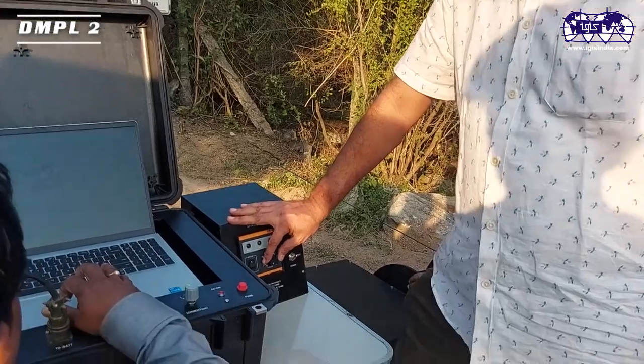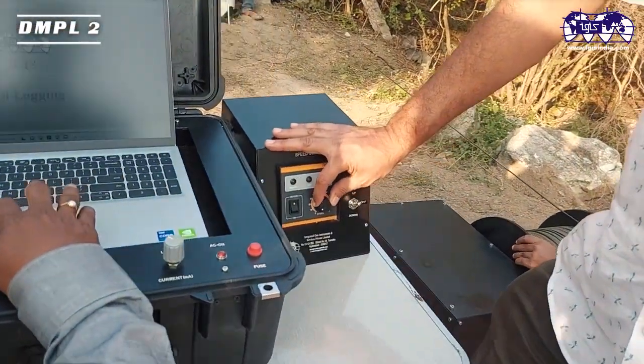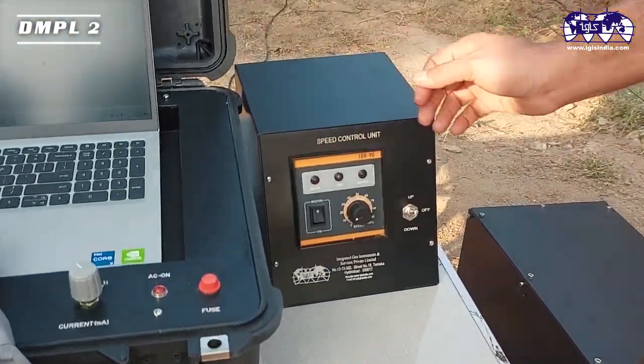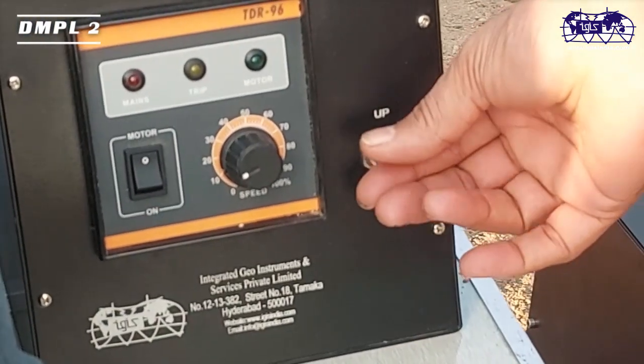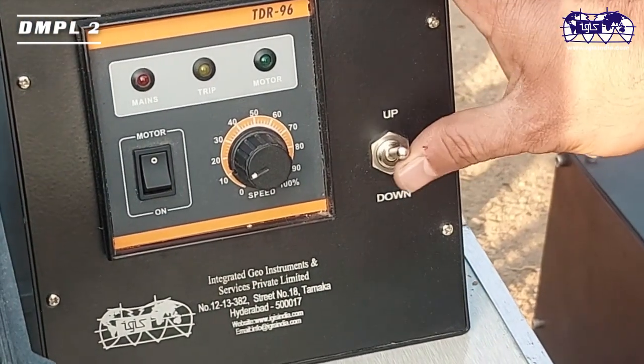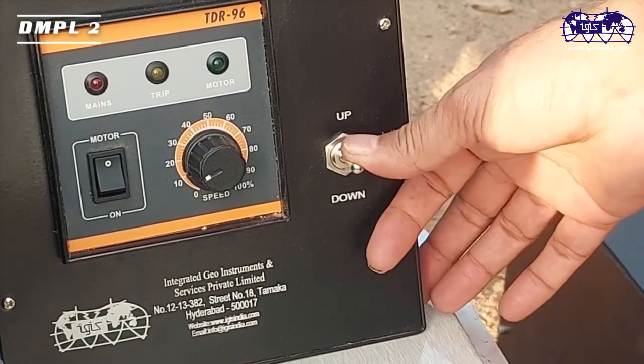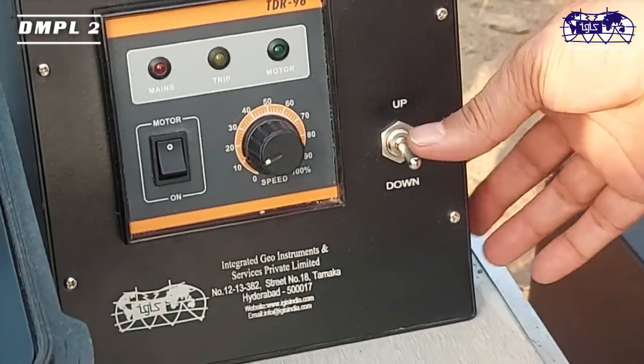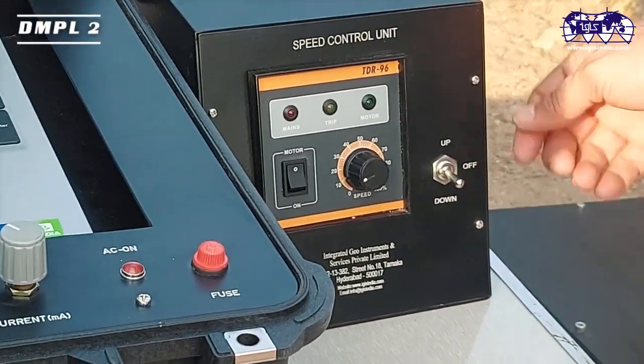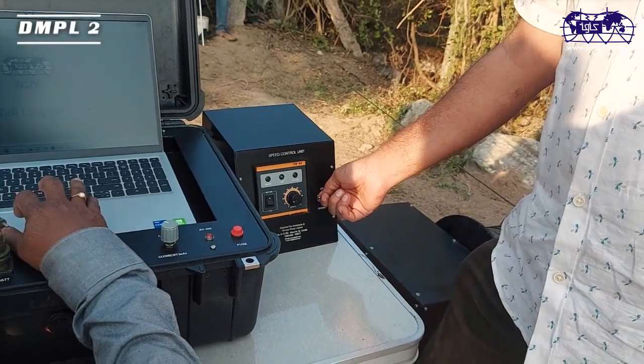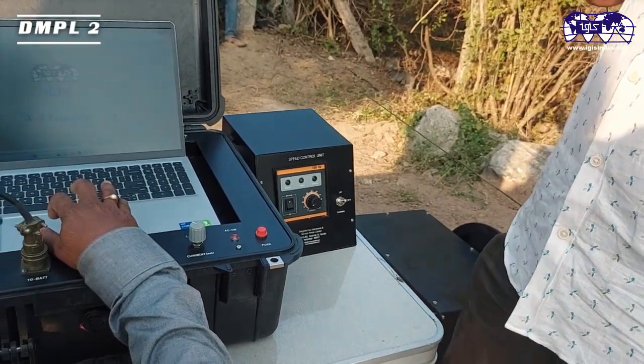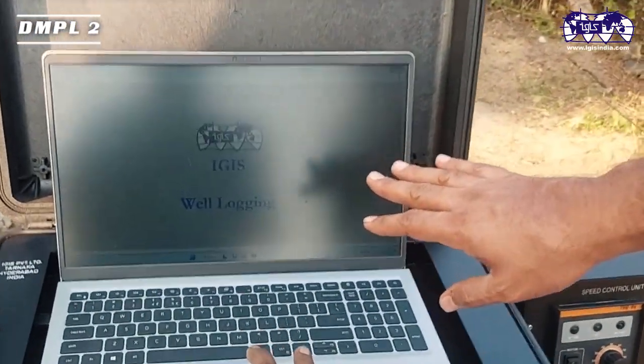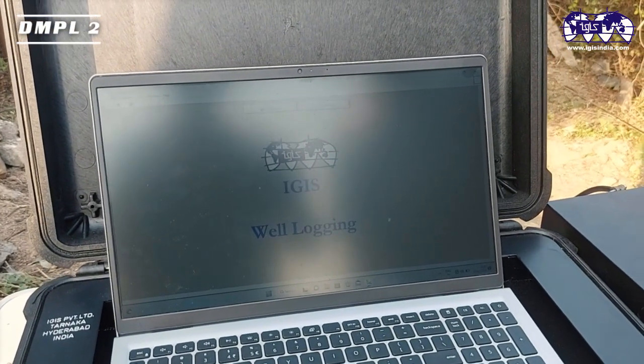When you are using the motor to control the speed, we have the speed controlling switch, and we have an option of up logging, off, and down logging. During the down logging, you position it in the down option, and during the up logging, you position it in up logging to drive the probe up. Here we have already opened the application, and now the operation is up logging.